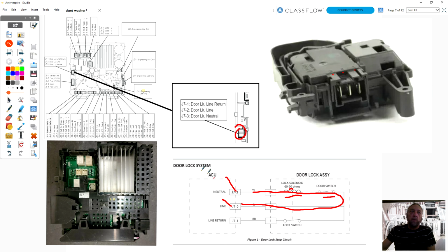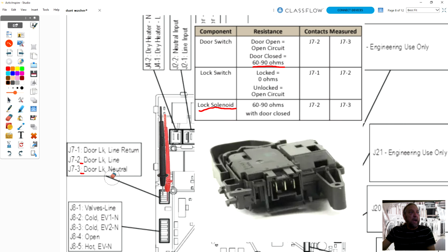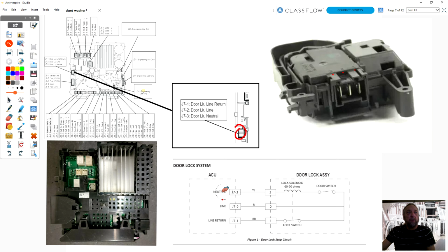Okay. What would I do to test it? First thing I want to do is put my voltmeter on line and neutral, which is 2 and 3. I'm going to go back to the diagram here. 2 and 3. And I'm going to press start. I'm looking for 120 volts. Just because it says line and neutral there, that doesn't mean line and neutral is there once the machine's plugged in. It just means that that terminal is the line 1 coming into it, and that's the neutral coming out.